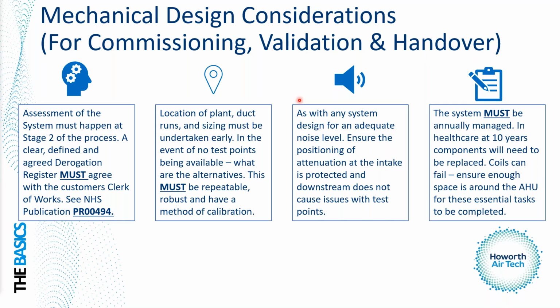And it's not acceptable if a designer has missed off a VCD to balance a low-level extract on an opposed blade damper, for example, within an operating theatre. That's just going to send the noise level straight through the roof. We need an adequate place for the VCD further downstream from the diffuser, and adequate places to test that as well.